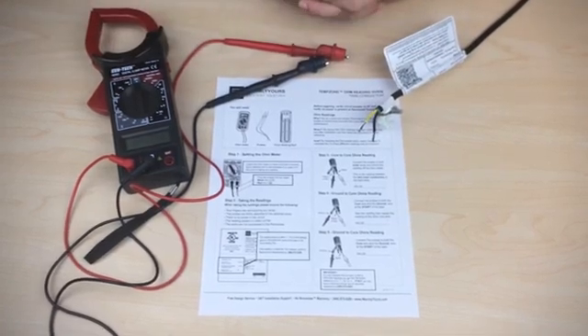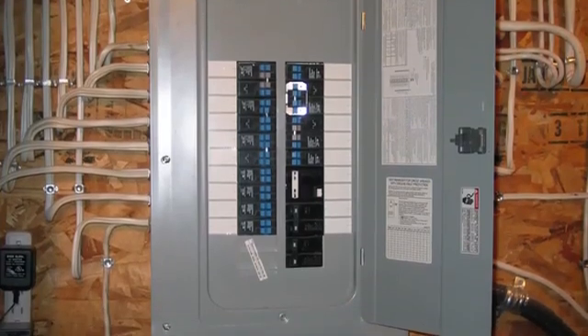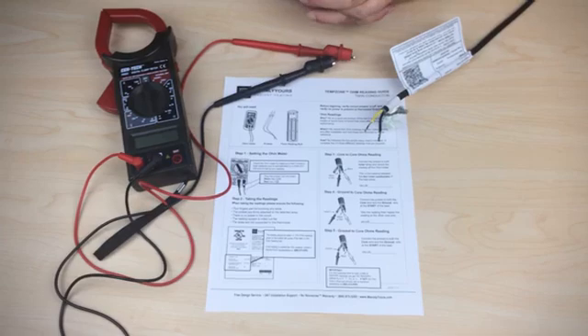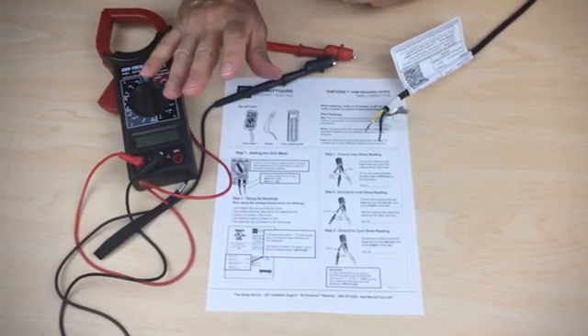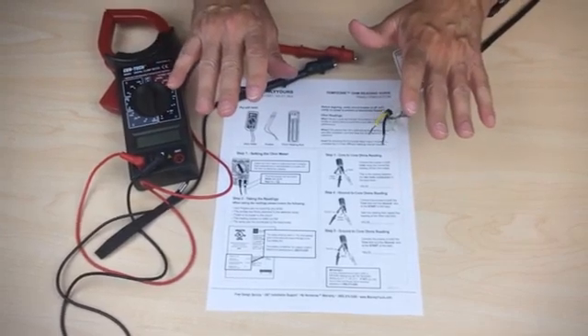Sometimes it's because you have a GFCI protected circuit breaker in your circuit breaker box. One important thing to remember is if you have a GFI circuit breaker in your box and you have a GFI controller in your thermostat, those two could fight one another.